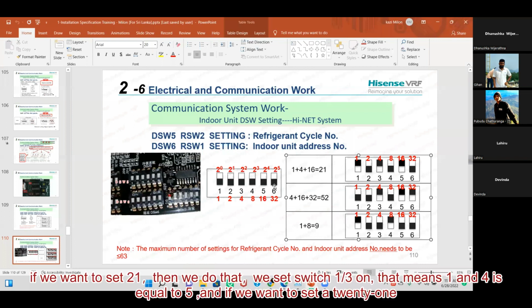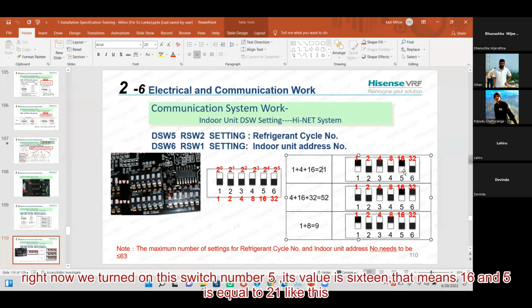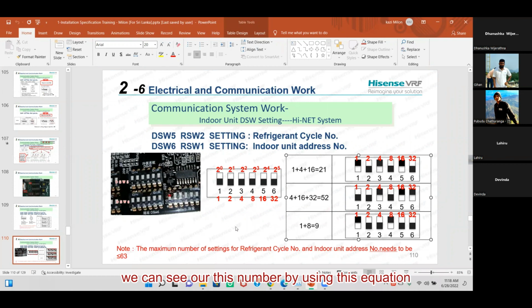If we want to set 21, then we need to turn on number 1, which is 1, and we need to turn on number 3, which is 4, and 4 and 1 is equal to 5. We want to set 21, and right now we turn on number 5. Its value is 16. That means 16 and 5 is equal to 21. Like this, we can set our address number by using this DIP switch.